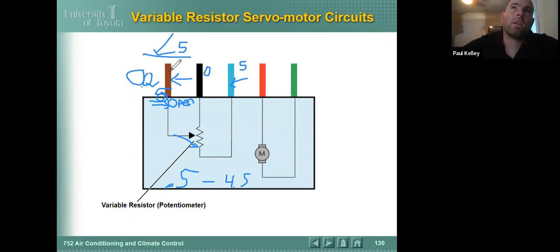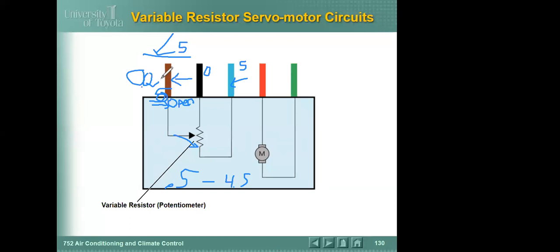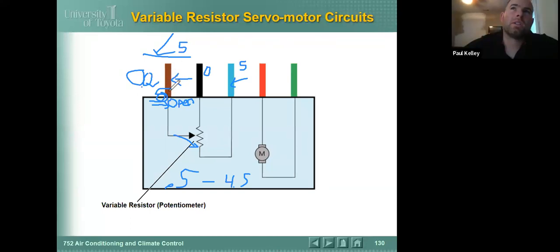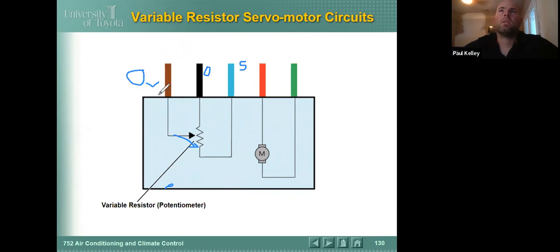So a lot of times we're going here and looking at the signal, and if the signal's 0, it's either because it lost its 5 volts, or there's an open on the signal. Those are the two, right? If we lost 5 volts here, that's going to read 0. If we lost the signal, that's going to read 0. Make sense? Okay, now let me switch it up so you can understand what I'm saying. If it was reading, let's just say, 5 volts on the brown wire, what are your thoughts?